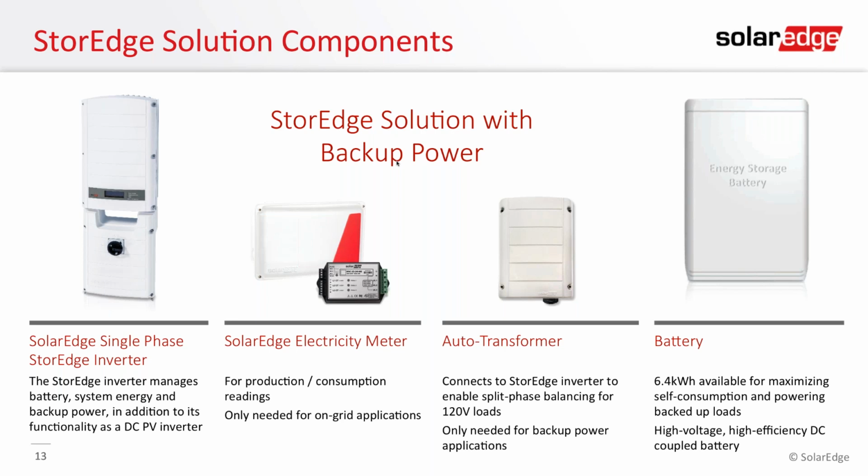That inverter is effectively the same as every other SolarEdge 7600 inverter. The difference is in what we call the BCU portion, which is the bottom half. You'll notice that the disconnect portion there is considerably larger than our other inverters, and the reason for that is there's quite a bit of technology built into that, specifically the input for the batteries, the pairing on that for all the communications that are associated between the battery systems and the inverter, as well as the automatic transfer switch, which allows the system to go into backup mode and isolate itself from the grid. So that's what's going on in there.